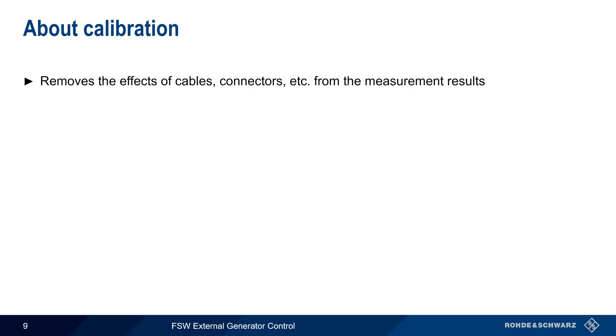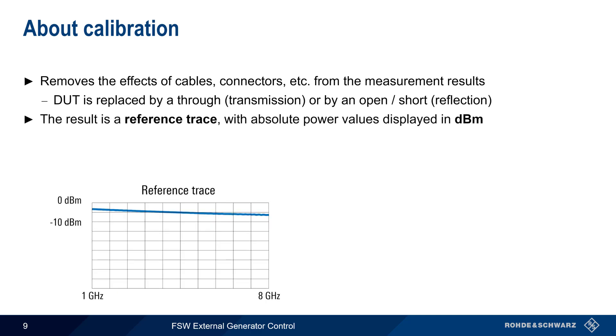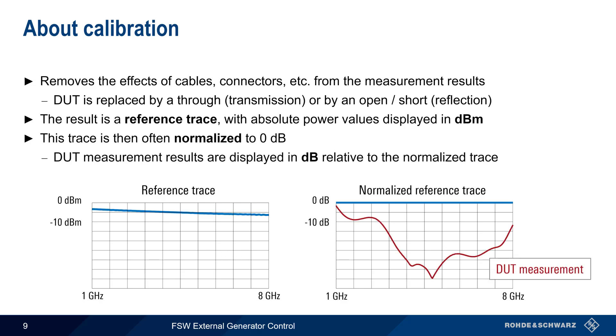Next we'll discuss calibration, which is the process by which the effects of cables, connectors, etc. are removed from the measurement results. Calibration involves replacing the DUT with a THRU in the case of transmission measurements, or with an OPEN and/or SHORT in the case of reflection measurements. The result of a calibration is a reference trace, which shows absolute measured power values in units of dBm. For network measurements, this trace is usually normalized to a 0 dB straight line, and measurements of the DUT are shown in units of dB relative to this normalized reference.